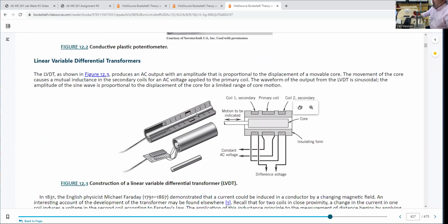There are two secondary coils on the outside of the primary coil. Those secondary coils pick up voltage inductively from the primary coil, but the amount of voltage picked up on the secondary coils changes with the core position. As the core moves up and down, more or less voltage is evident on the output, so we can use an RMS multimeter to read the output and calibrate that to position.